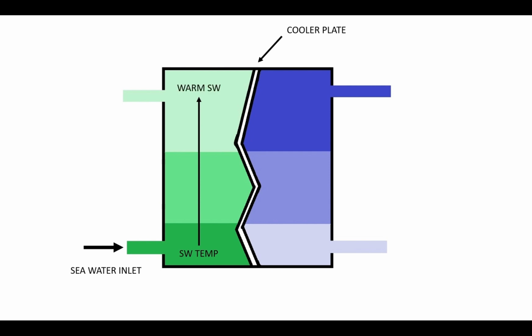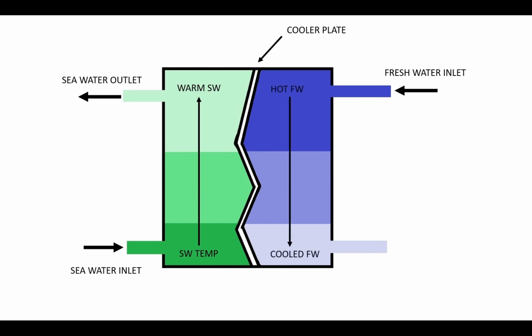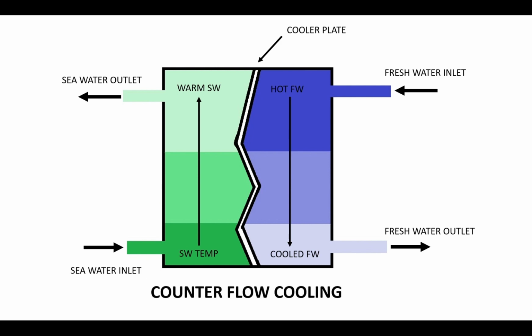Let's check the flow of fluid. Cooler plate. Seawater inlet is at the bottom, with normal seawater temperature passing through the plates going up and becoming warm water. Seawater will then leave the cooler at the top. The hot fresh water inlet is located at the top, passing through the cooler from hot fresh water to cooled fresh water, leaving at the bottom. This flow of fluid is called counterflow cooling.